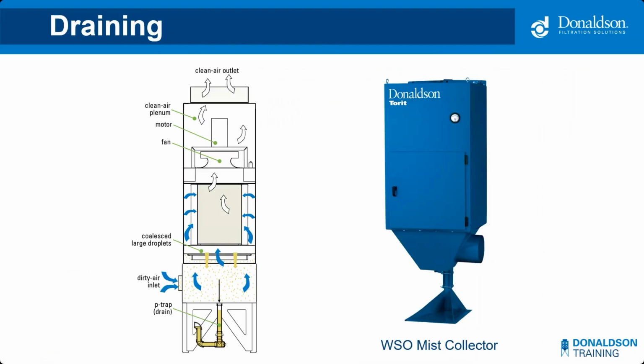Another very simple type of cleaning method is draining collectors. If you specify a collector for an application that generates mist, think wet machining typically, it will most likely utilize a collector that drains. You can see an example here called the WSO. The dirty air inlet is towards the bottom, on the bottom left. The flow of the air is upwards through the collector through a series of filters. The mist droplets collect on those filters, coalesce into larger droplets, which eventually gravity will pull them down against the airflow and drain them down into a P-trap at the bottom of the collector.